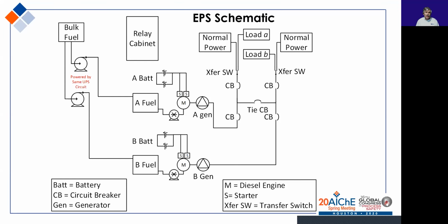The generators are diesel driven. We have a bulk fuel tank with two different transfer pumps powered by the same UPS circuit to transfer the fuel to the A fuel tank and the B fuel tank. Each genset has a dedicated fuel pump, two starters, and two batteries. And then each genset has circuit breakers as shown, and generator A has a transfer switch.